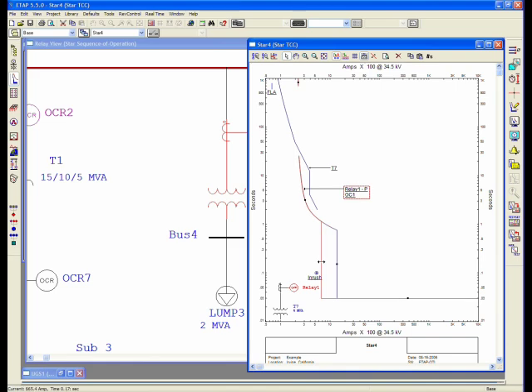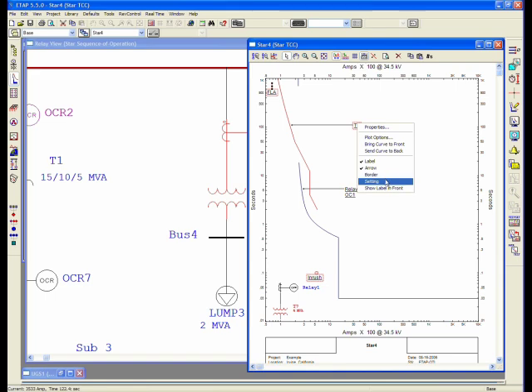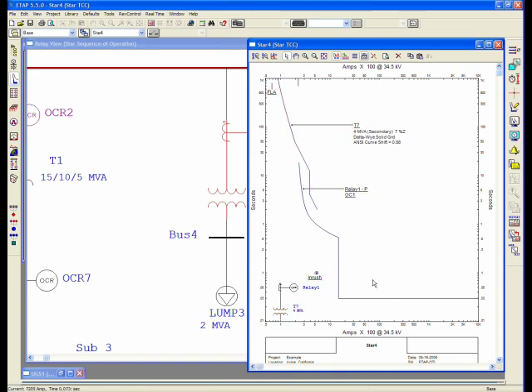You also have an issue with the mechanical damage point that might be crossing this point. But what we're showing on the transformer is the transformer damage curve and the in-rush point, and in addition to the full load amp mark here.